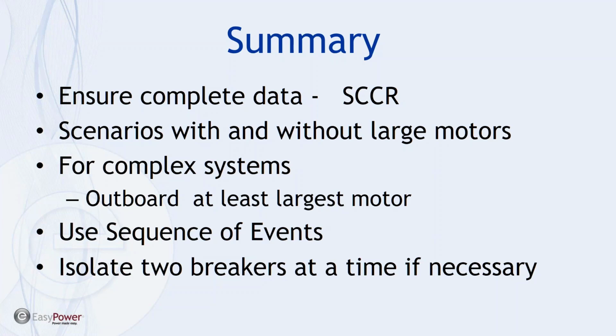in terms of being able to isolate and separate the different breakers, if you have similar loads, it may be necessary in that case to use an isolated or discrete representation of the bus. In any of those cases, I would recommend using sequence of events, and then the process is to work with 2 or 3 breakers at a time and coordinate from the bottom up.